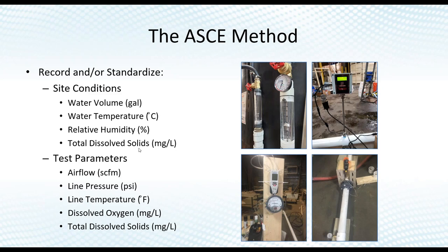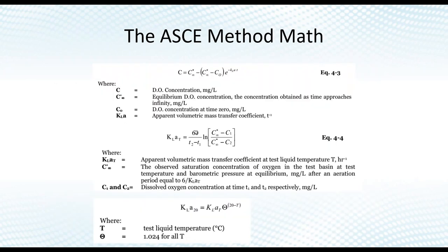It's critical to accurately measure airflow — without knowing how much air is going in, you can't know how efficient the system is. We use rotameters, orifice plates measuring differential pressure, and mass flow meters. We also record air temperature because hotter air is more expanded — it will look like higher volumetric flow, so we must adjust for pressure and temperature of the air to standardize across technologies. After all the data is collected, significant math is done, which I won't detail here.